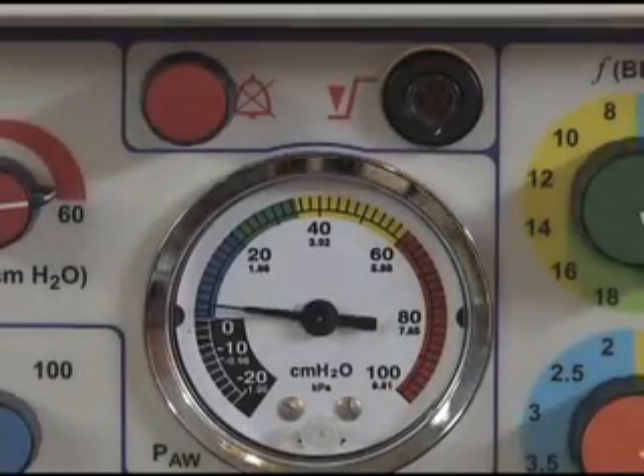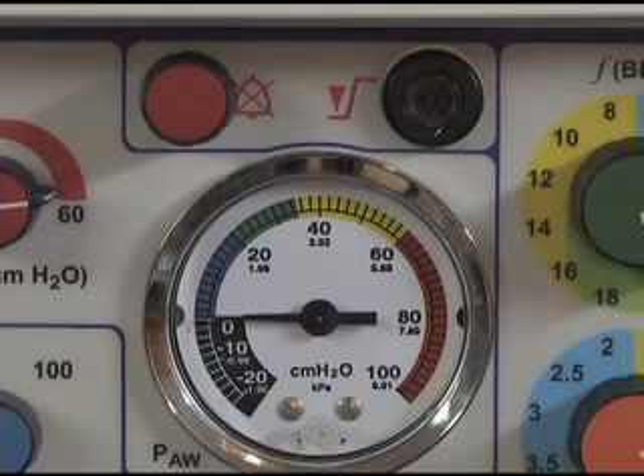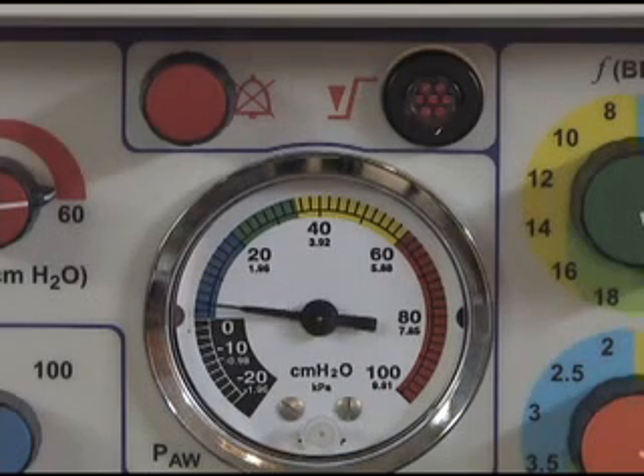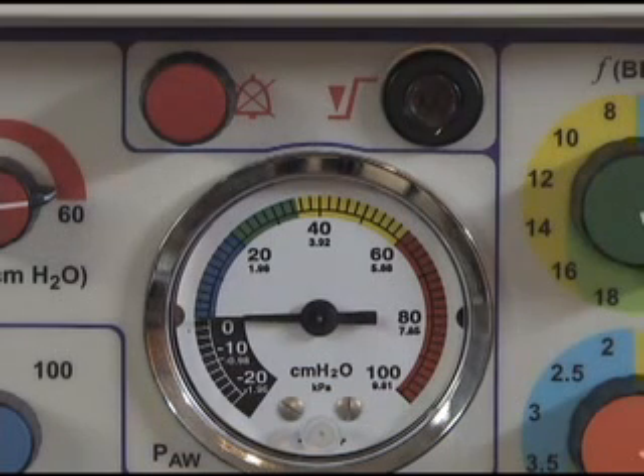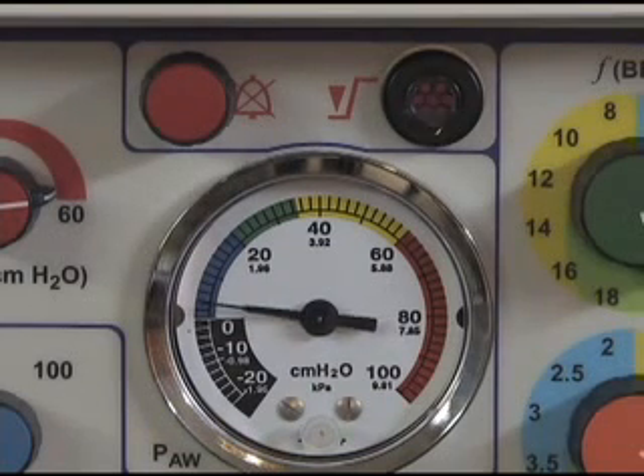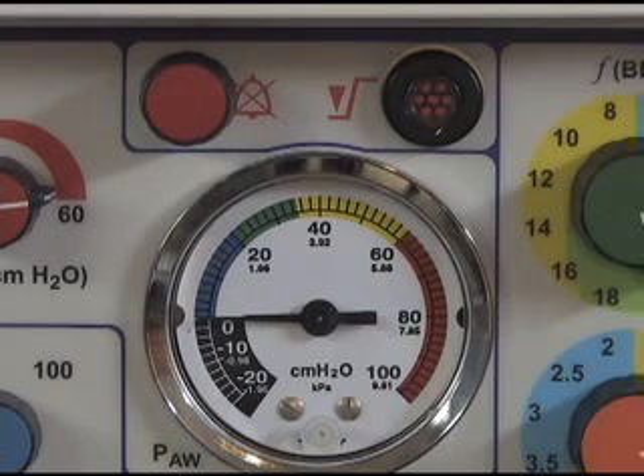The Breathing System Integrity Alarm, BSI alarm, is provided to warn the rescuer of any change in the ventilations. This totally pneumatic alarm activates when the pressure in the patient circuit fails to reach a minimum of 10 centimeters of water during inspiration, indicating that either the circuit has become disconnected from the patient or that an insufficient tidal volume is being delivered for the lung capacity of the patient. In addition to the high-frequency, high-pitched audible alarm, there is a red flashing visual indicator to warn the rescuer of a problem in the patient's airway.